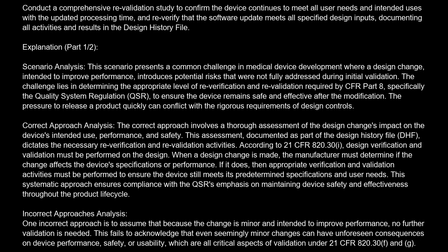Correct approach analysis. The correct approach involves a thorough assessment of the design change's impact on the device's intended use, performance, and safety. This assessment, documented as part of the design history file, DHF, dictates the necessary re-verification and revalidation activities. According to 21 CFR 820.30(i), design verification and validation must be performed on the design.